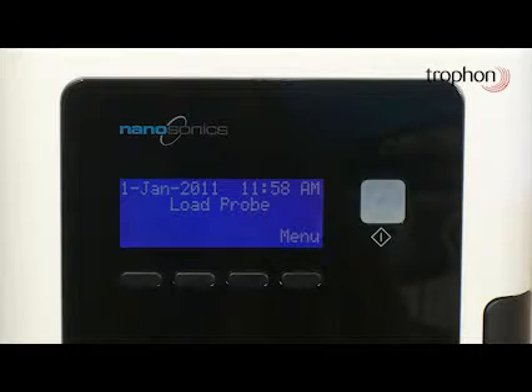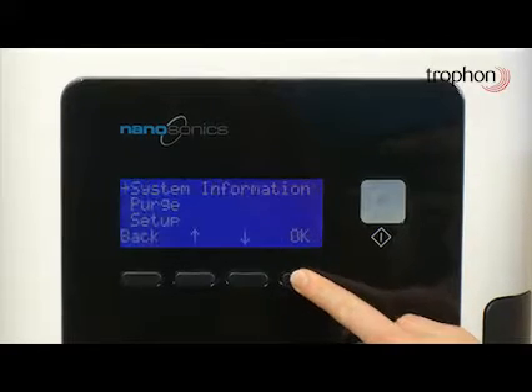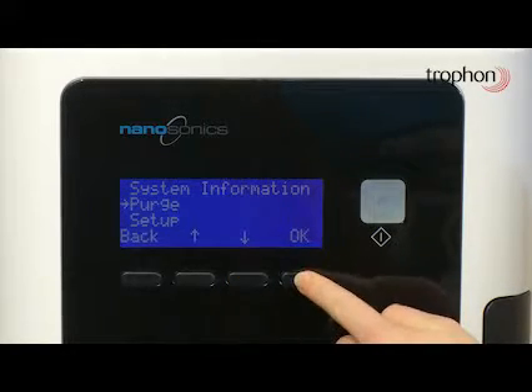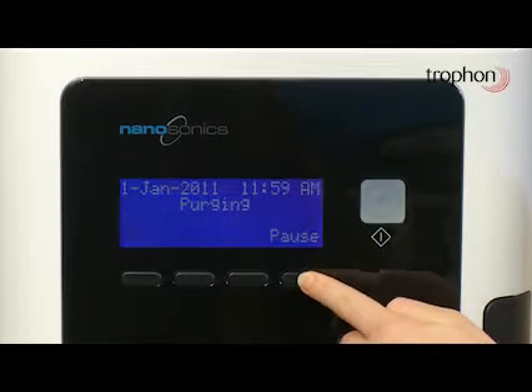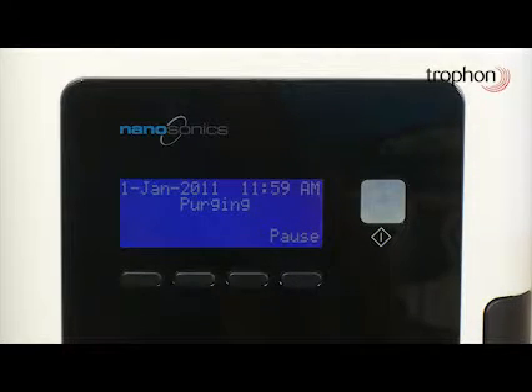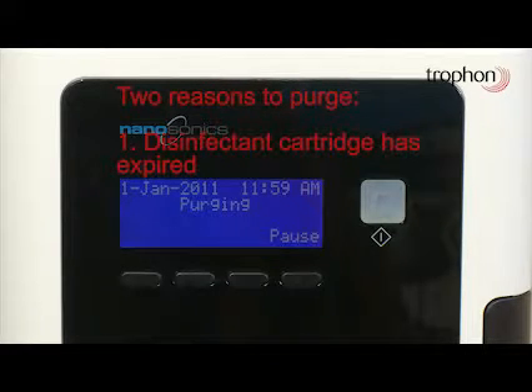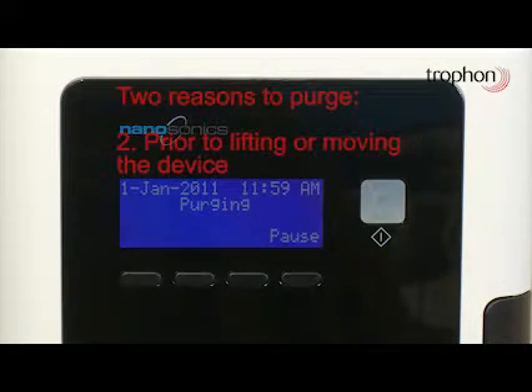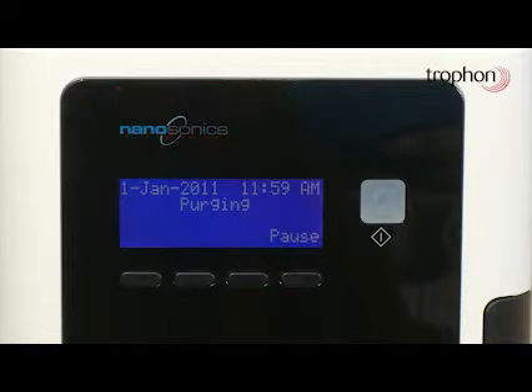If the disinfectant has expired within the device, or if you wish to move the device, you will need to remove the disinfectant. The purge cycle performs this function. The cartridge expires 30 days after loading it into your device. There are 2 reasons to run a purge cycle. 1. If the disinfectant cartridge has expired, the device will prompt you to run a purge cycle. 2. Prior to lifting or moving the device, you will need to use the menu and select Purge manually.